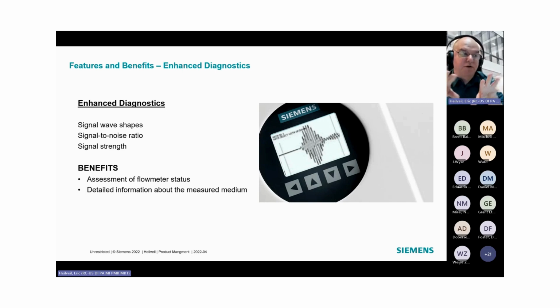As you move the transducers around and as you alter how they're mounted and the information within the device, all of which can be altered. So you can set it so that the transducers mounted on the pipe have a single path like that, or you can move them further apart and have a multiple traverse signal, so that the signal bounces off the top, bounces off the bottom, bounces off the top. That would be two traverse. You can change all of that.